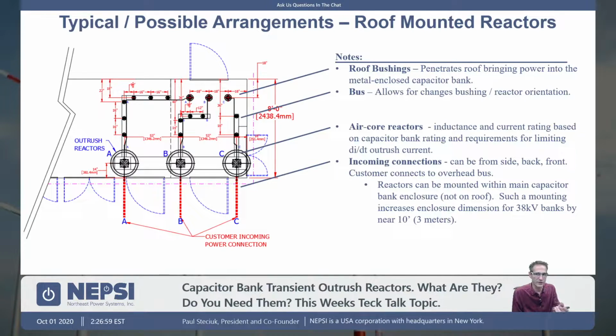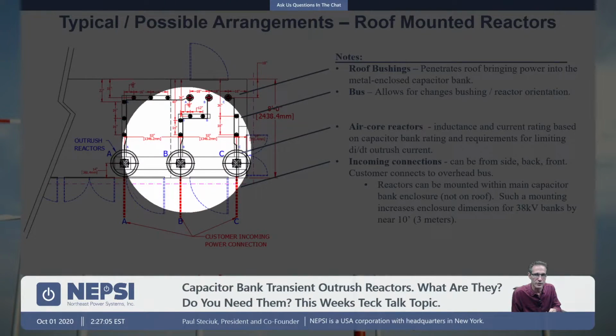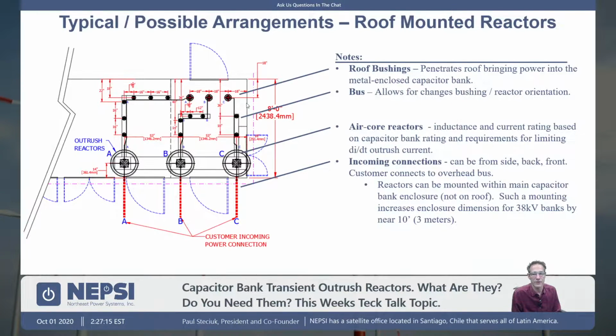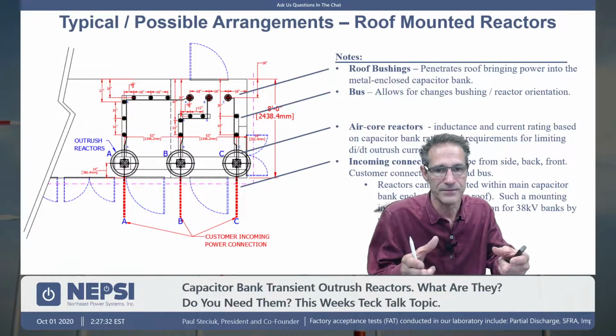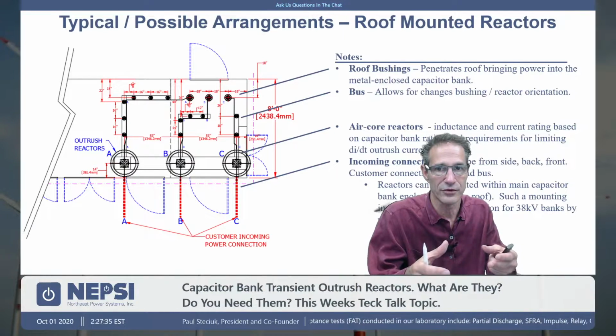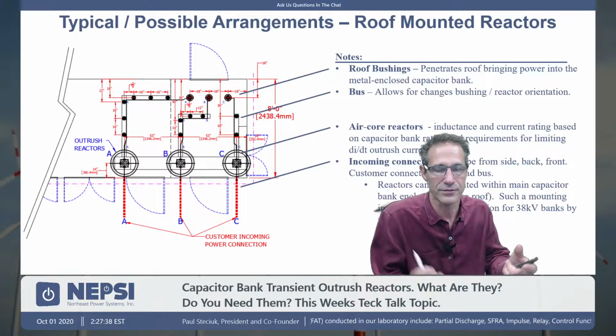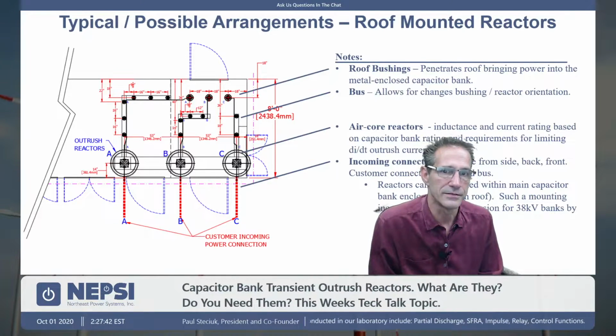Sometimes it makes sense to orientate the equipment in a different direction. When we do that, we might change the buswork structure on top in the layout of these bushings here, such that we can have cables come in through the back or through the sides. So it really depends on the substation design, but just know that the outrush reactors, typically the space required between them is greater than what would typically be required for the incomer of the capacitor bank. But with bus work up on top, we are able to orientate the incoming power cables in any of the three directions, either the front, the back, or the side. And this is something that is really an option. We're going to actually look at a piece of equipment out back that will show how we're doing this.